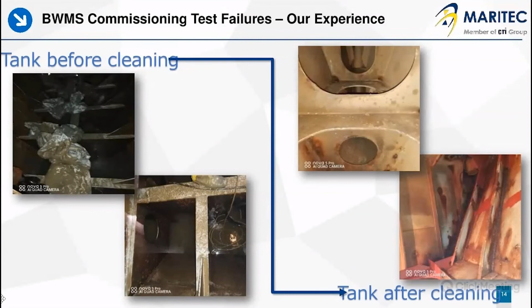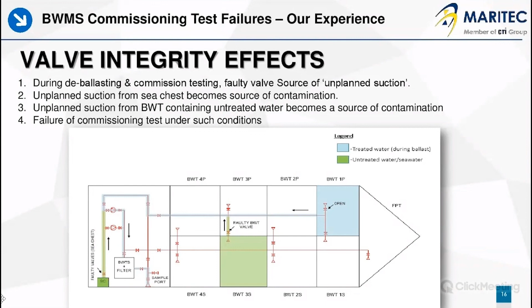Some other reason for failed tests is the valve integrity effect. What this actually means is that if the pipeline is not in a proper, good condition before sampling and during the analysis, it can cause problems, because we have suction from either the sea chest or from tanks that contain untreated water.